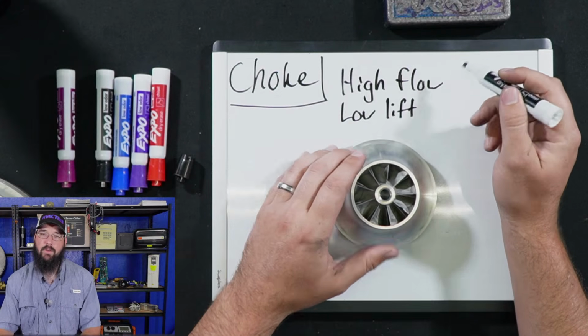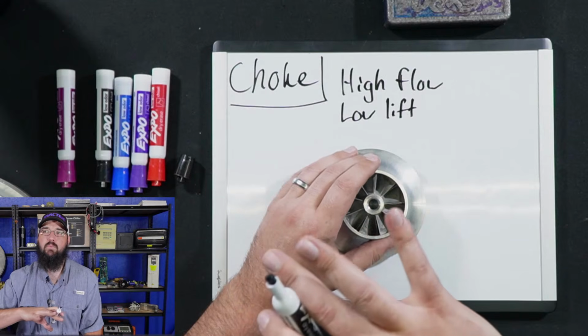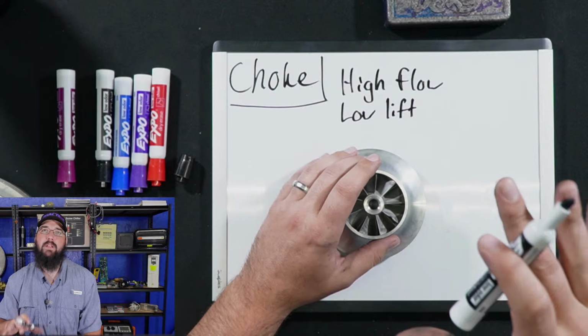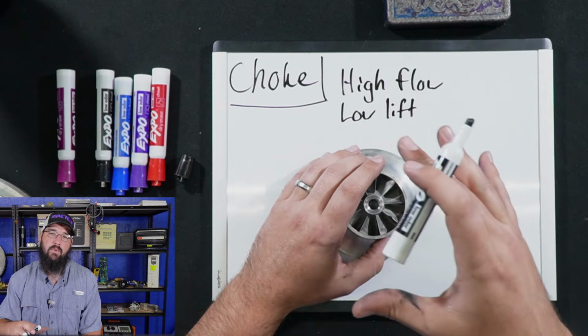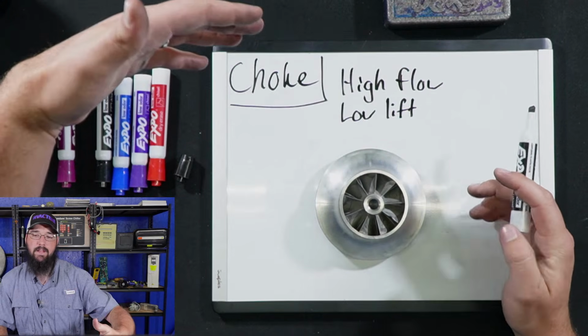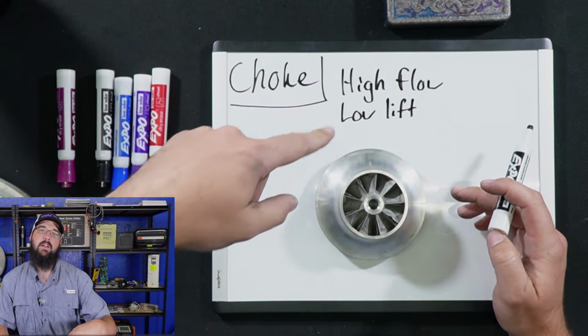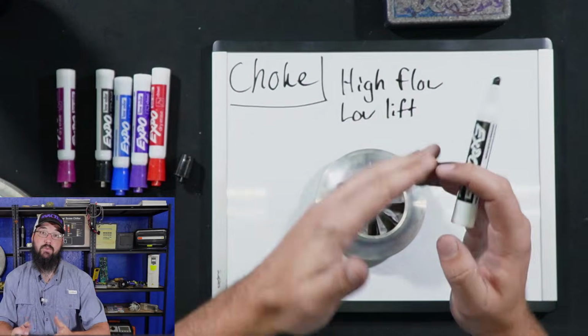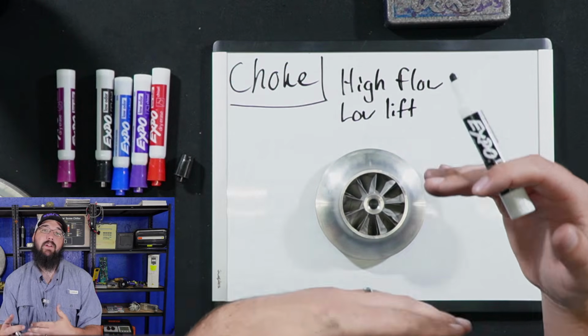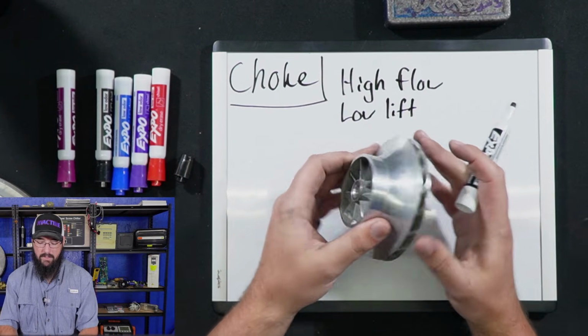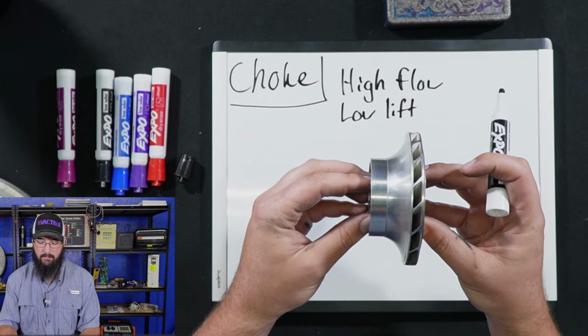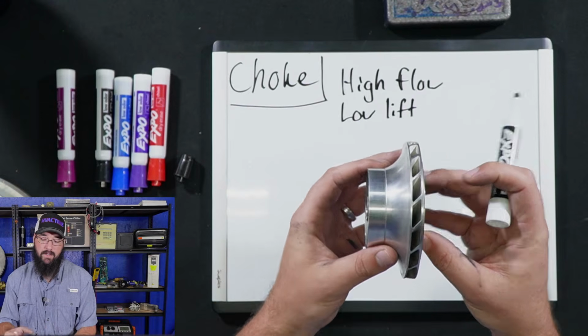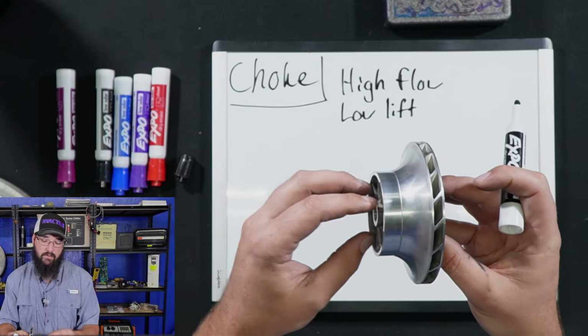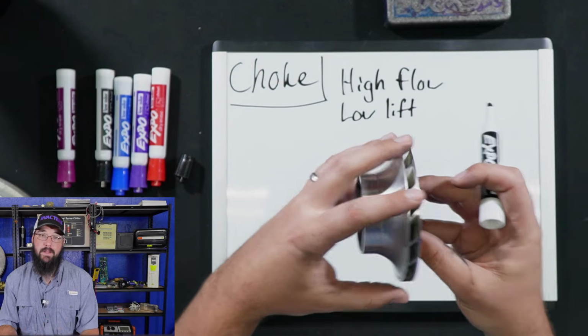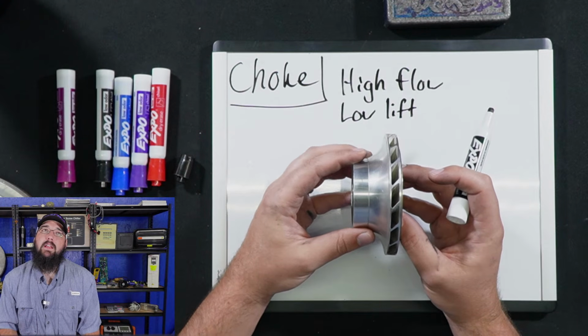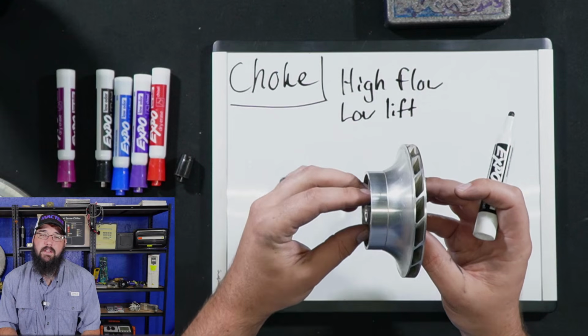But if we have a high load, we get to this point where the impeller becomes unstable in its ability to flow, because we're moving more mass CFM through the impeller than what the impeller can maintain due to a low lift. Having lift is important for having the machine function correctly. We do need lift across this impeller to keep the loads balanced across it. So when we get really low lift, we have a ton of high flow. We can get to where we can begin to choke the impeller, and it'll create a bunch of instability in the impeller itself.